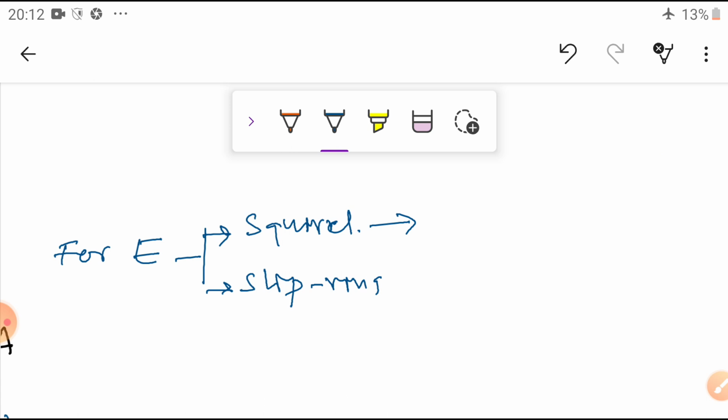Here the mechanical loss is negligible, actually zero, because the rotor is blocked, and iron losses are very low compared to the copper losses. So in that condition, whatever the wattmeter shows, WSC, is equal to the total copper loss. Now what is the stator copper loss? This is the wattmeter reading.